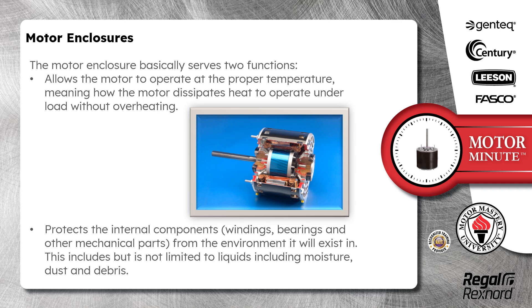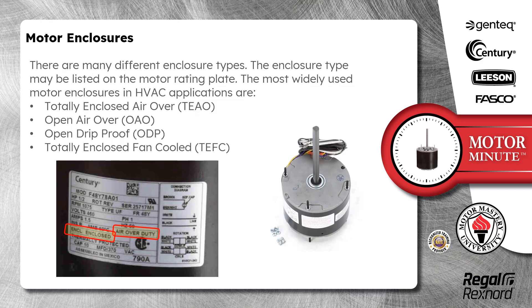This includes but is not limited to liquids including moisture, dust, and debris. There are many different enclosure types, and the enclosure type may be listed on the motor rating plate. The most widely used motor enclosures in HVAC applications are totally enclosed air over, open air over, open drip proof, and totally enclosed fan cooled.